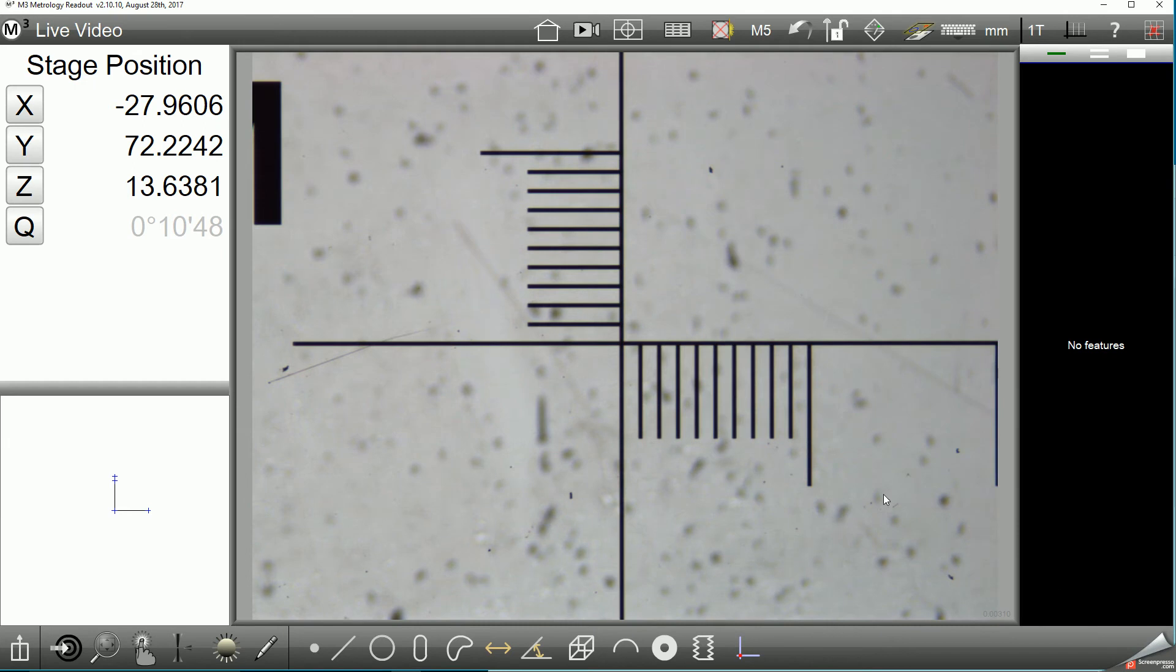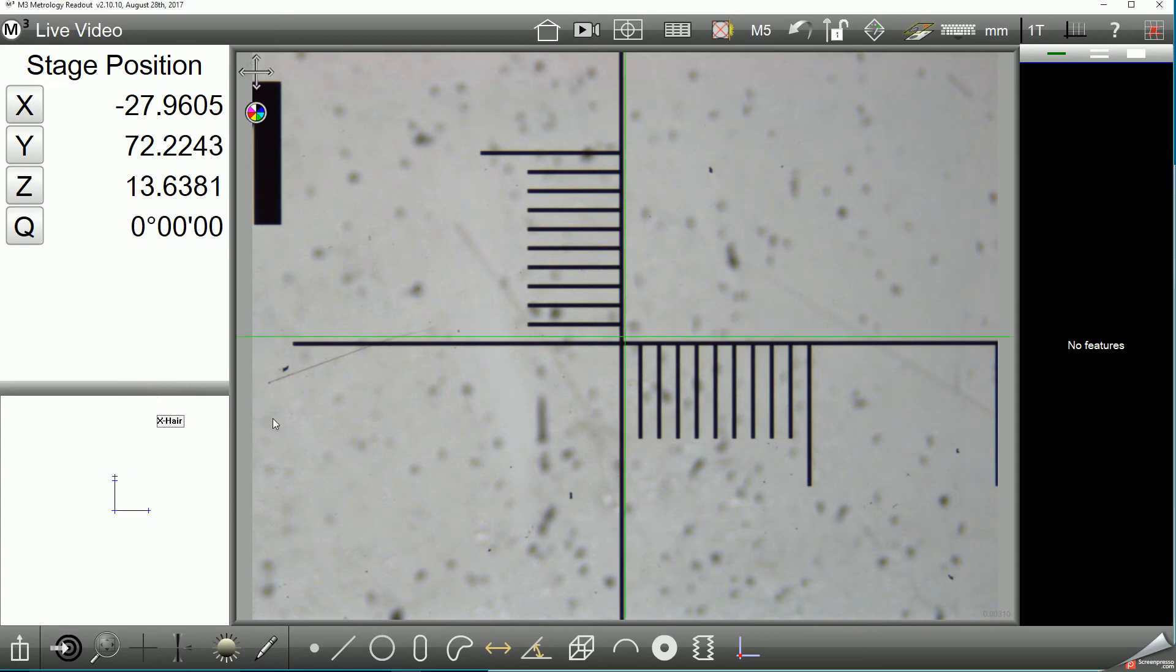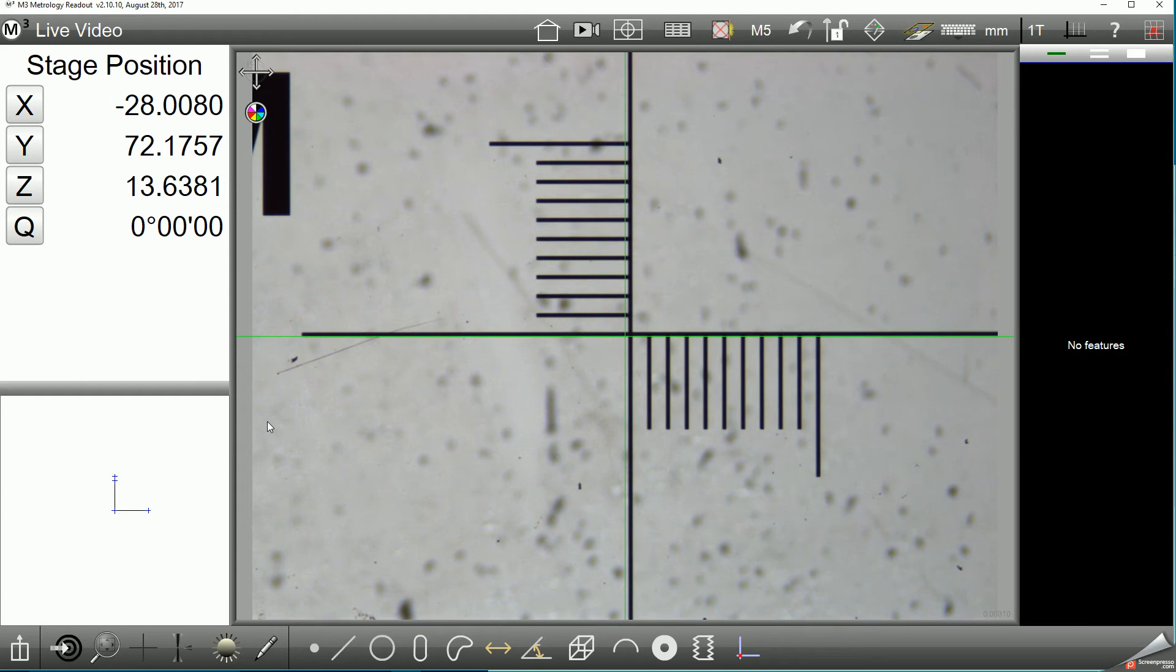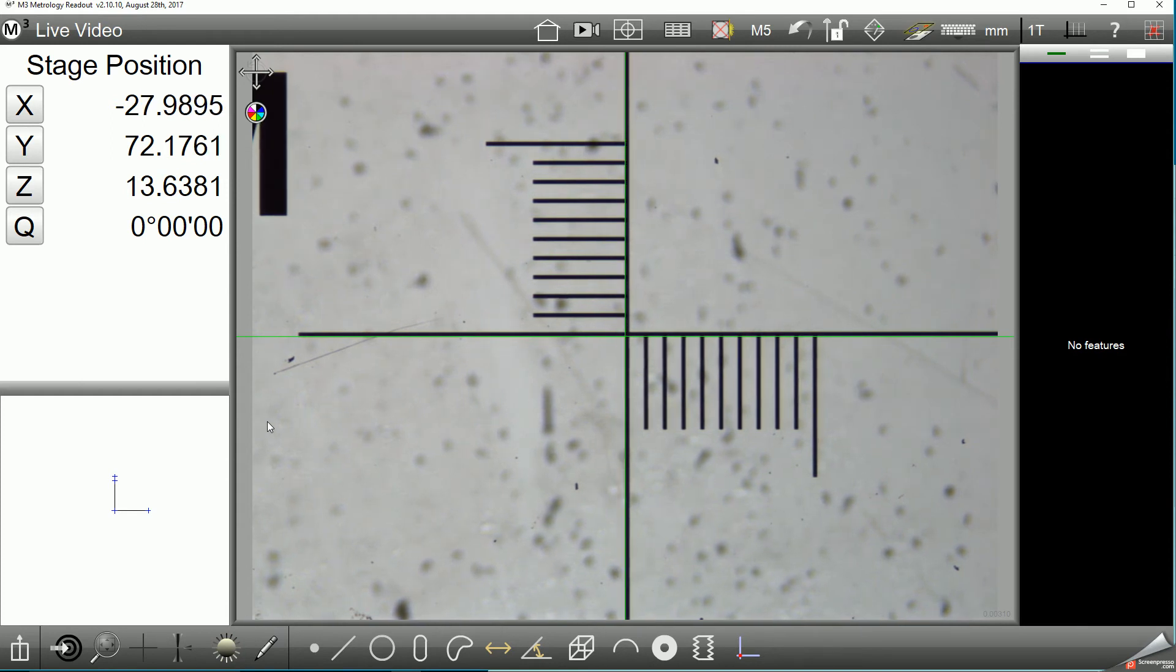I've got my calibration artifact ruler placed on the stage. I'm going to go ahead and select the simple crosshair which I'll be using to probe the data that will be used to enter my correction information into the system.